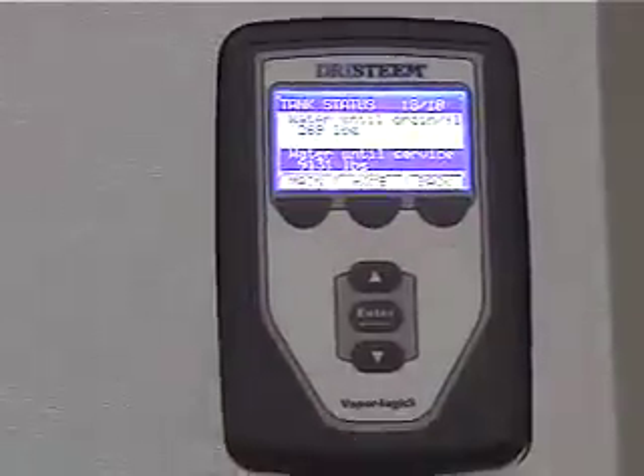So, and then I actually allow these to run, I think it's 10,000 pounds of steam before we require service. It's going to come up and give you guys an alarm to tell you, look at it. And the only way you're going to know really how good your water is, is by getting in here and maybe in 3 months, open one of these up and look at it. If it looks good, don't worry about the rest of the rooms. Go another 3 months and pick another one. Open it up, it looks good, hey, we know we can go 6 months, you know what I mean?